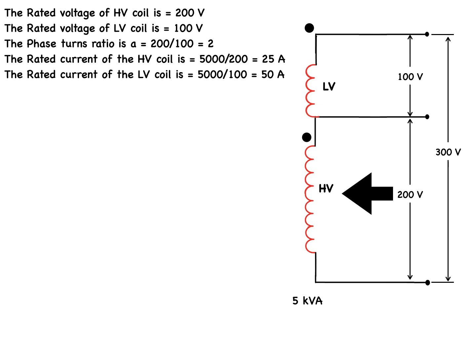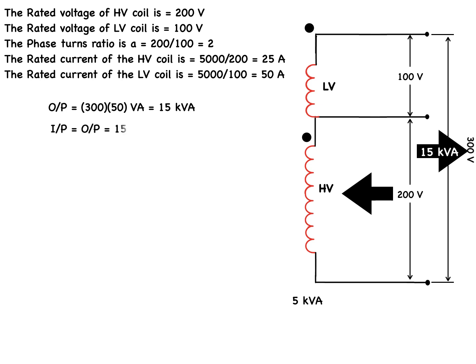Since the load is in series with the low voltage coil, the load current is the same as the current flowing through the low voltage coil. Thus, the maximum of 50 amps can be drawn by the load, otherwise we are overloading the coils of the transformer. The output kVA is equal to 300 times 50 VA, or 15 kVA, and the input kVA, of course, equals the output kVA, which is also equal to 15 kVA. The current drawn from the supply is the input of 15 kVA divided by 200 volts, which is 15,000 over 200, equal to 75 amps.